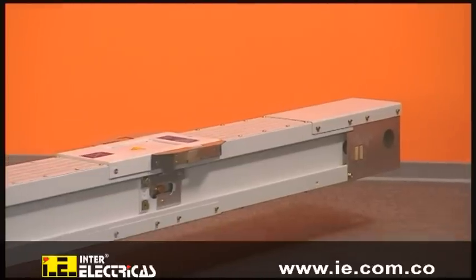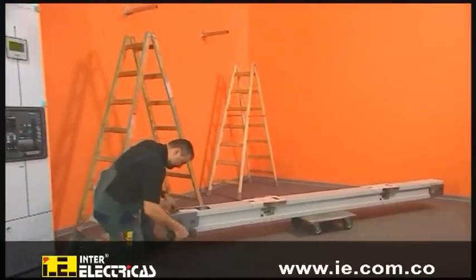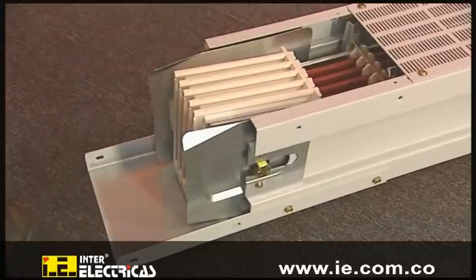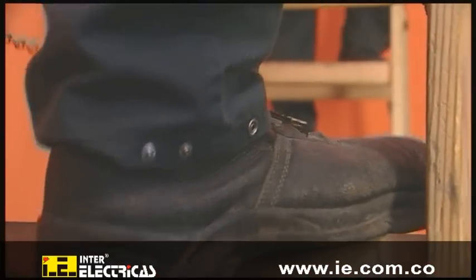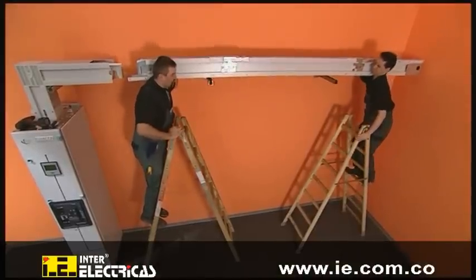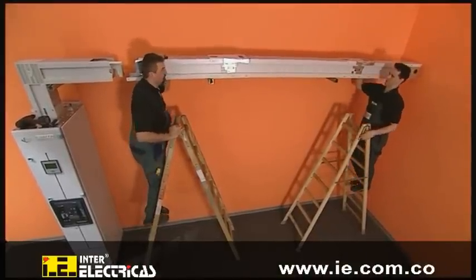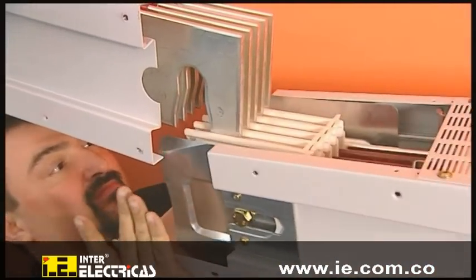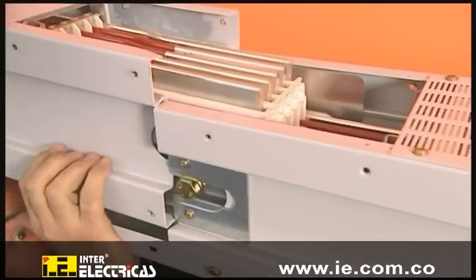The transport protection is removed from the trunking unit. The trunking unit is now mounted on the wall — it is placed on the previously installed fixing stands, then attached to the hook of the connector, which ensures correct phase assignment at the junctions between the trunking units.